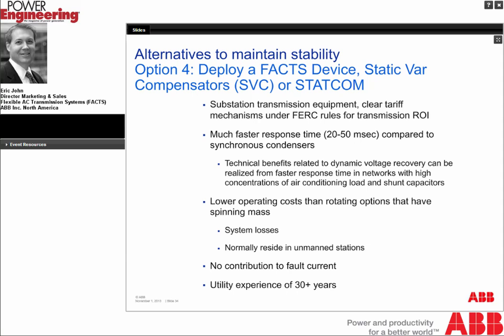The last alternative is the shunt FACTS device, a static VAR compensator, or a STATCOM. With an SVC or STATCOM, it is clearly substation transmission equipment. There are clear tariff mechanisms under FERC rules to earn a transmission ROI. You don't have a question about rotating apparatus and is it a generator or is it transmission. A FACTS device is capable of a response time that's much faster than a synchronous condenser or a generator for that matter. And there can be some technical benefits related to dynamic voltage recovery that you can realize with a faster response time. And this is especially true in networks where you have a high concentration of air conditioning load and shunt capacitors.